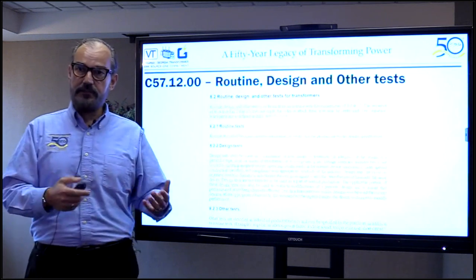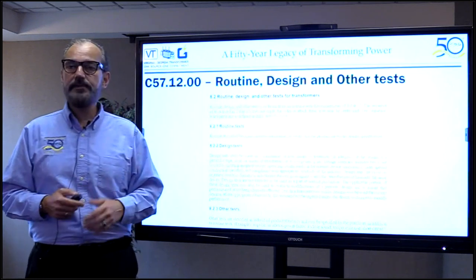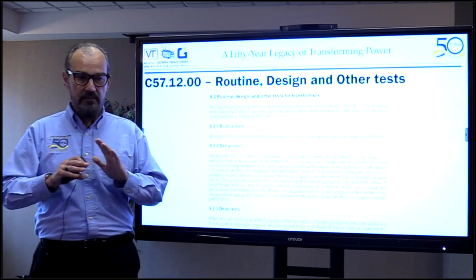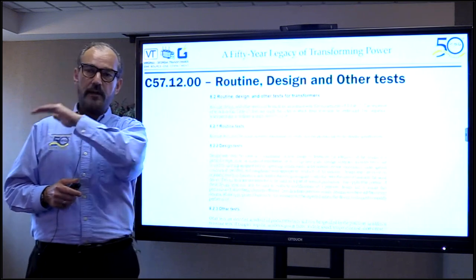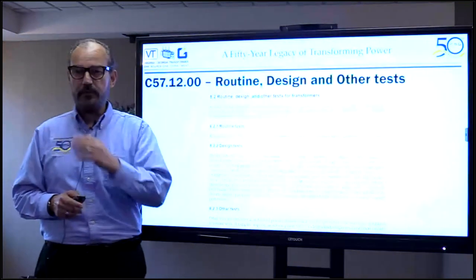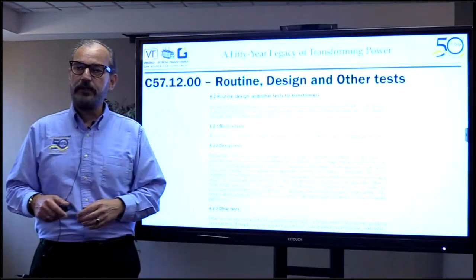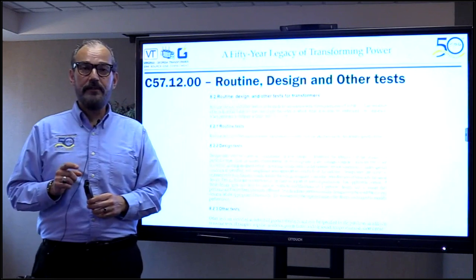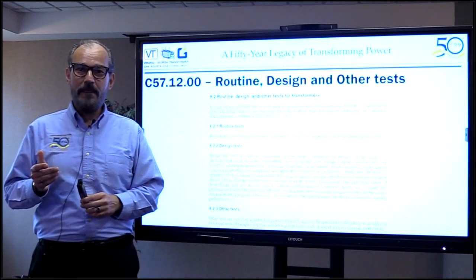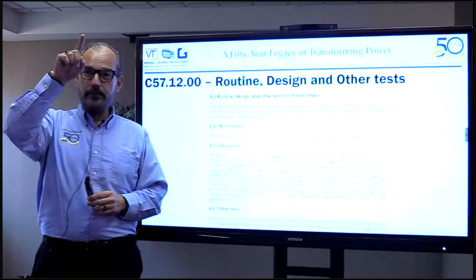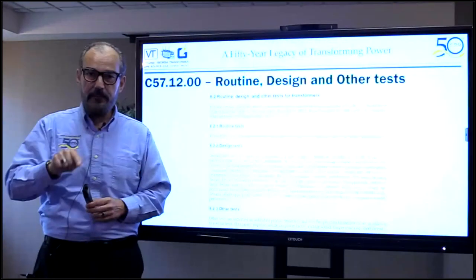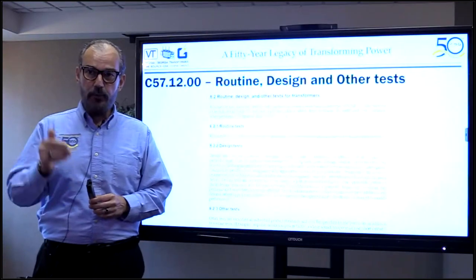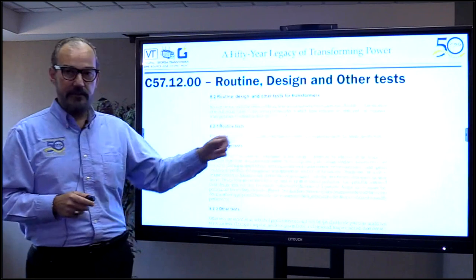You can ask for additional tests beyond routine tests, and many customers do. But if you simply specify testing to IEEE C57.12.00 and C57.12.90, the tables define what is required based on the class of the transformer. Routine tests must be performed on every transformer as stated.